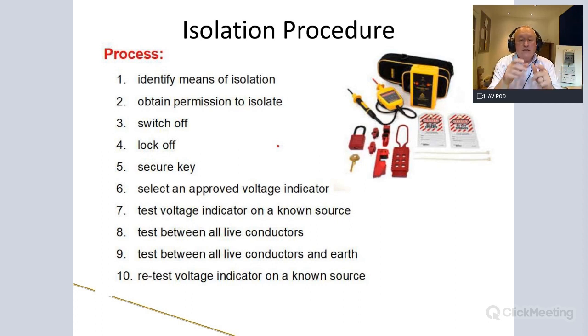Select the appropriate approved voltage indicator, which we've just seen, and test it on a known source. The known source in this case would be the proving unit. Then, whether single phase or three phase, it doesn't matter - you test between all live conductors, and then live conductors to neutral and earth. Then you retest the voltage indicator just in case it's gone faulty in the meantime.